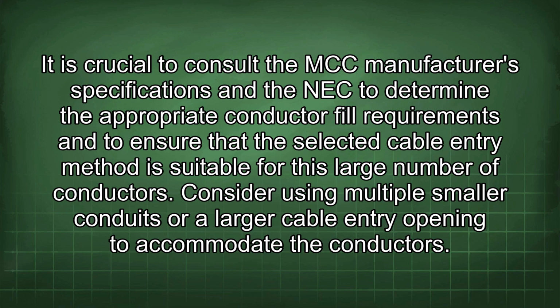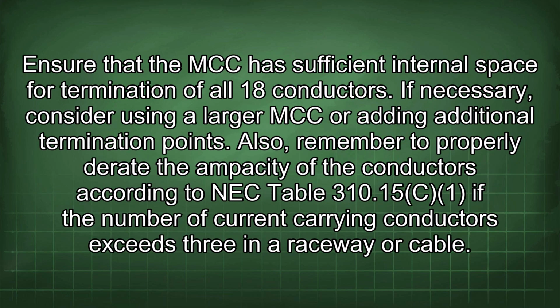Consider using multiple smaller conduits or a larger cable entry opening to accommodate the conductors. Ensure that the MCC has sufficient internal space for termination of all 18 conductors. If necessary, consider using a larger MCC or adding additional termination points. Also, remember to properly derate the ampacity of the conductors according to NEC Table 310.15 if the number of current-carrying conductors exceeds 3 in a raceway or cable.